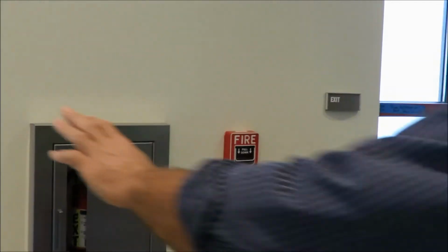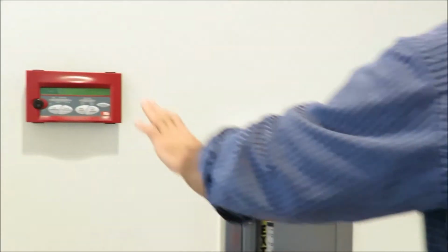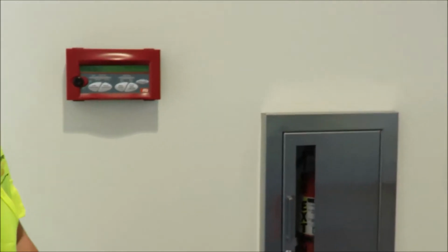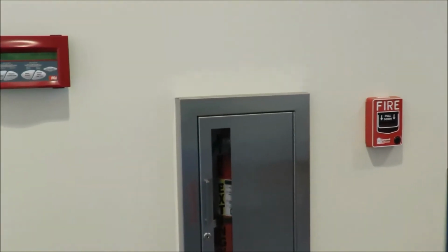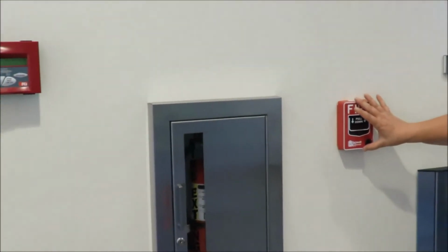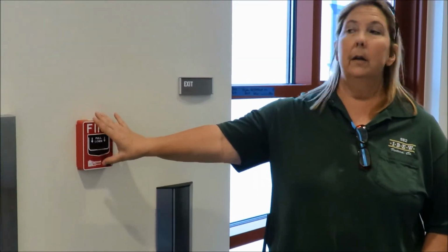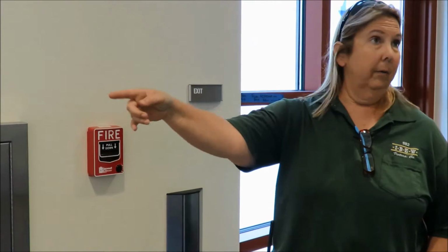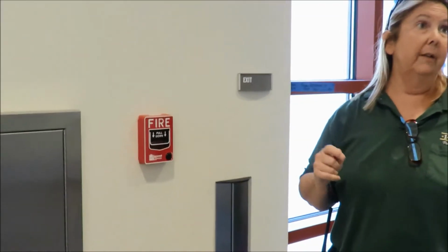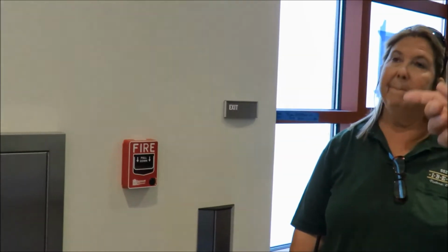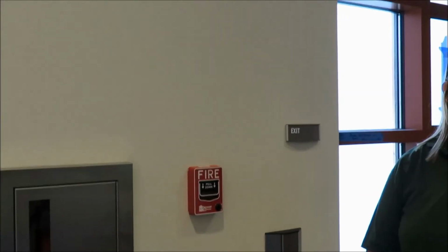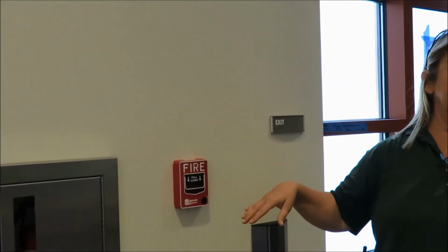Okay. Do you need to go to this panel or the one downstairs to reset the alarm? Yes, you do. And this only resets the pull station switch. Whatever activates in the field has to be in its normal state for the panel to reset. Okay, so it's a double reset. It's reset this, then go over here or downstairs to reset. Because if you shut the alarm off, I'm trying to get that. Right.